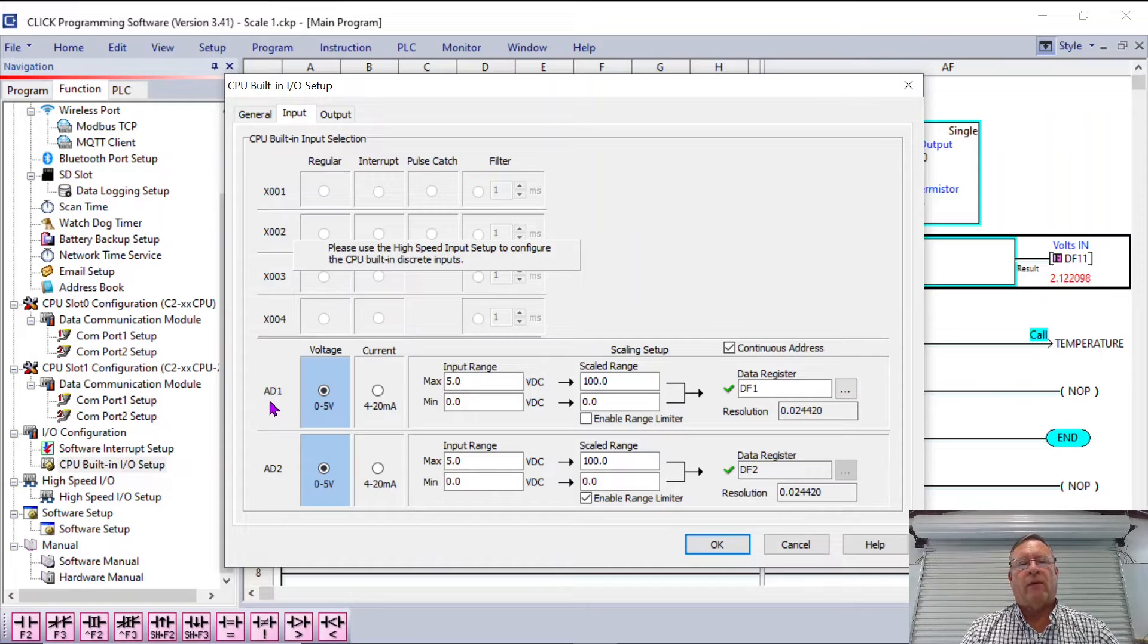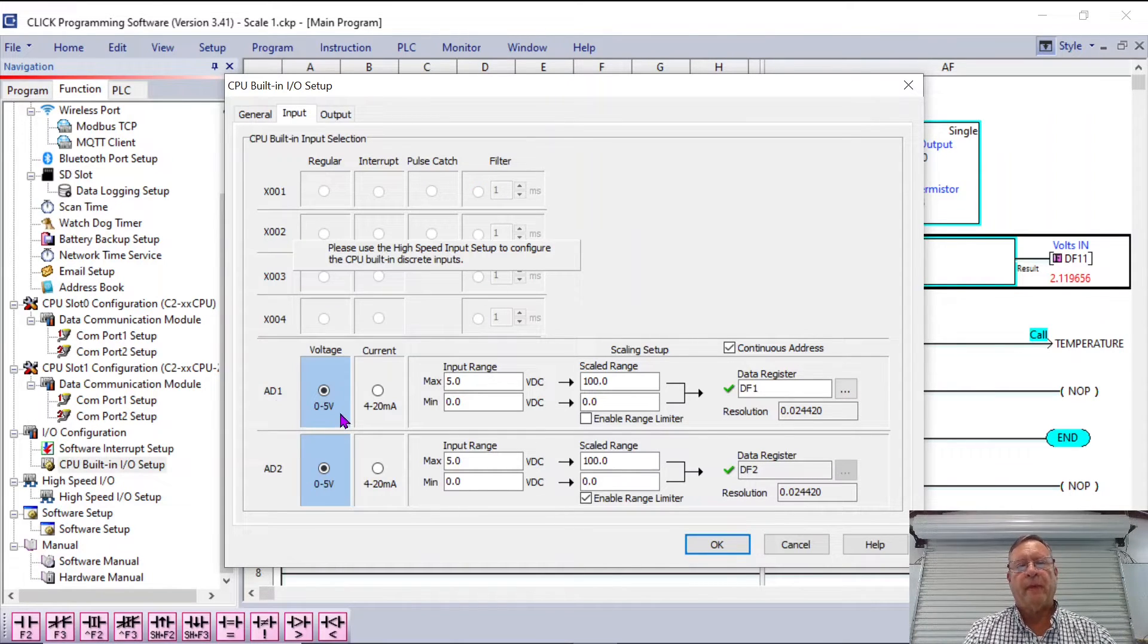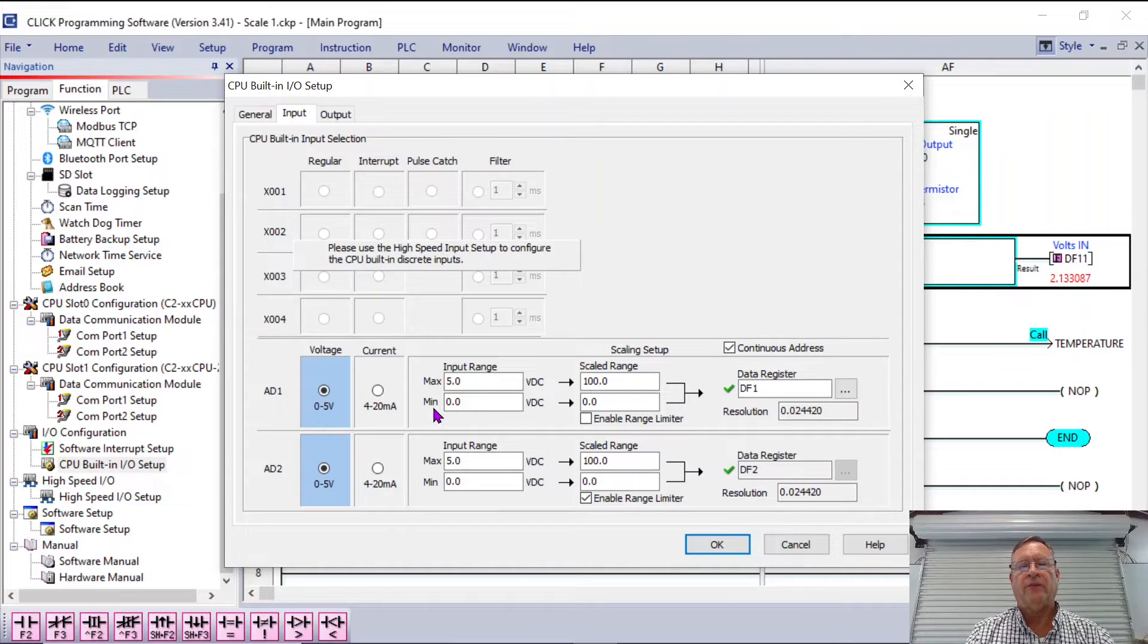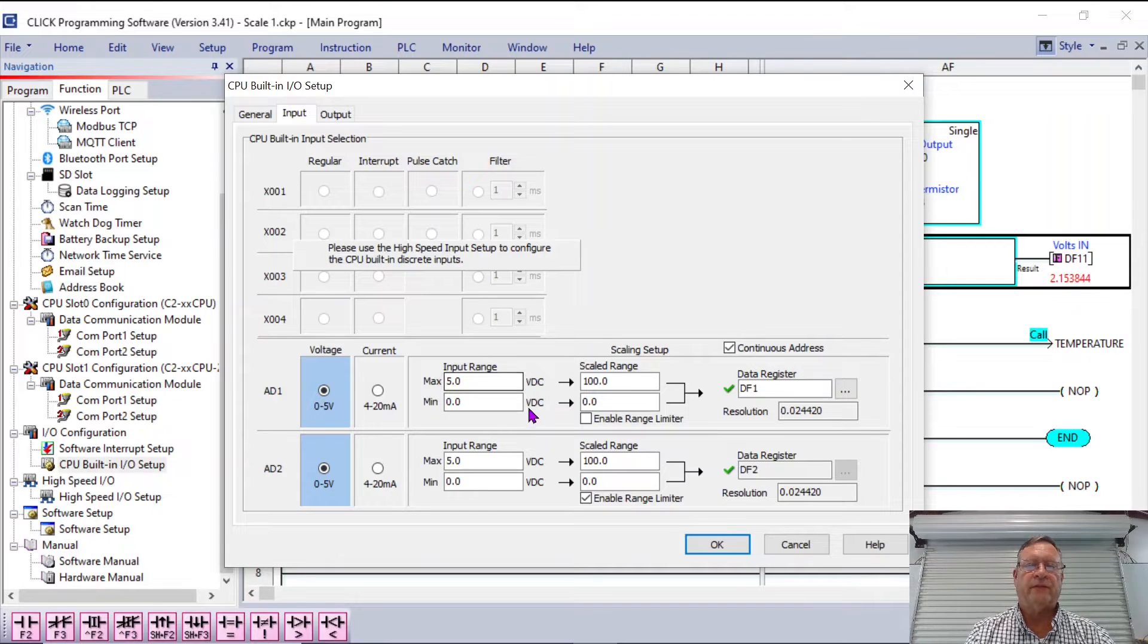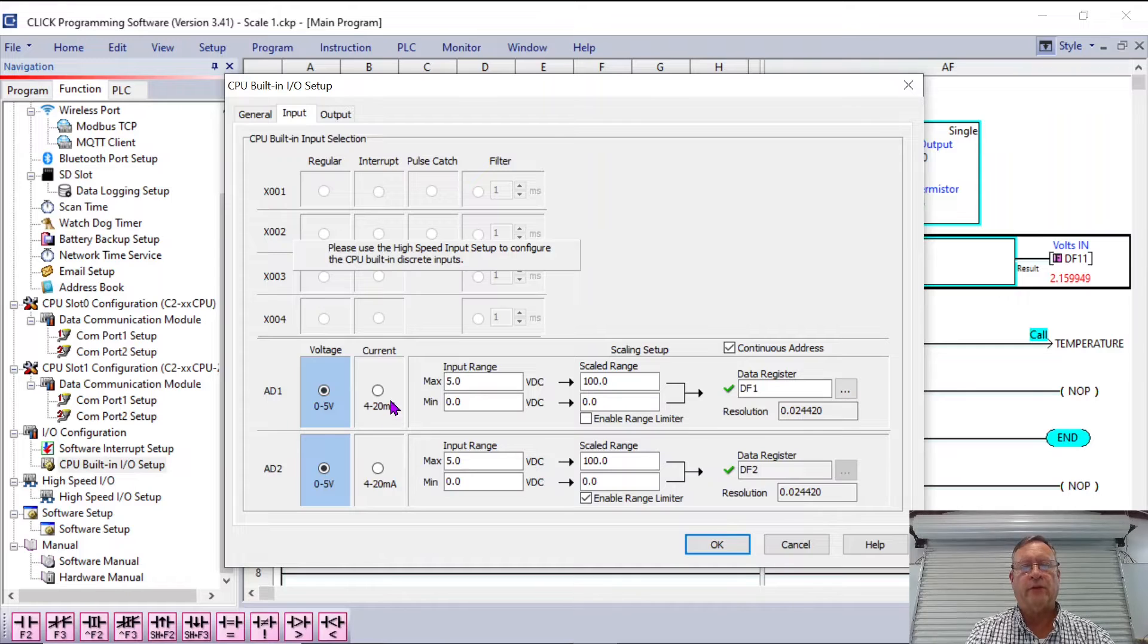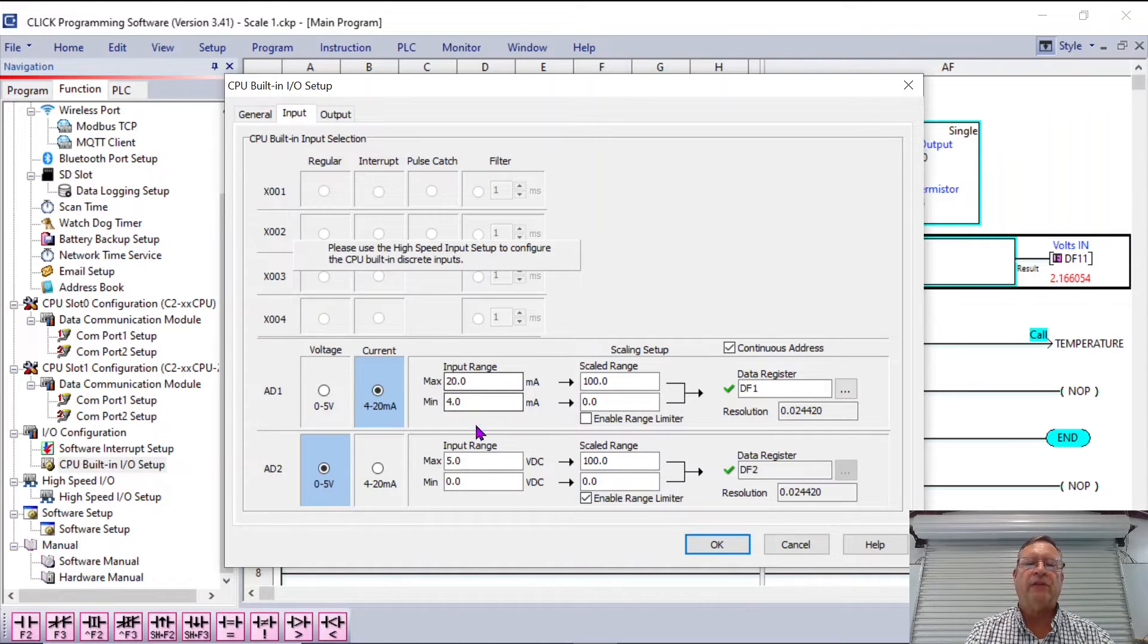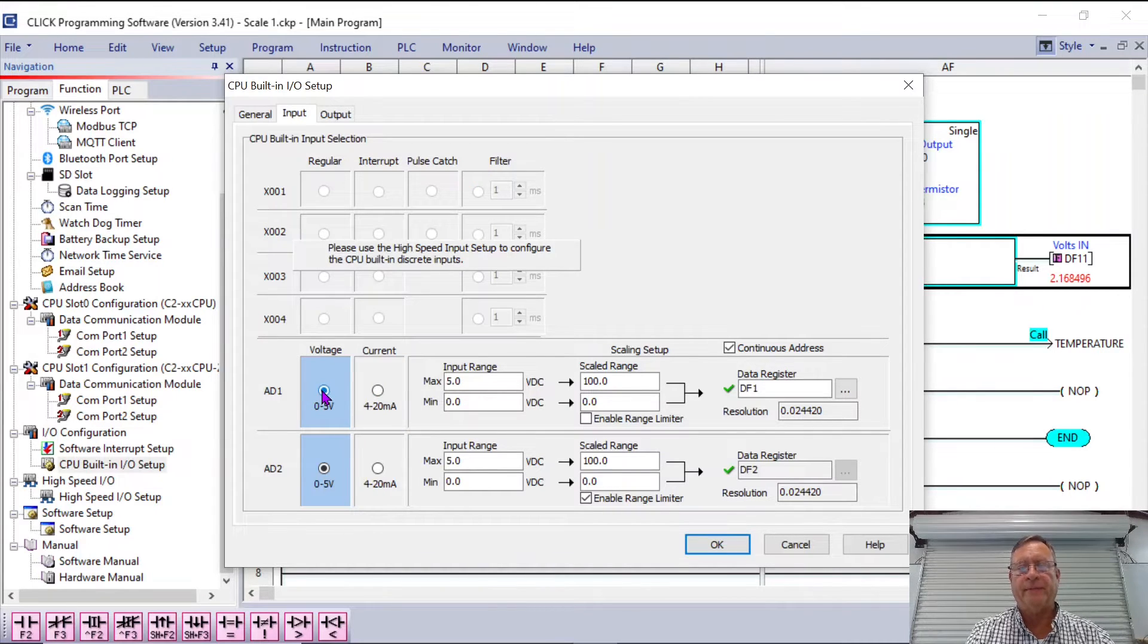On the analog to digital number one, I've selected the term, I'm physically connected to the terminal for voltage, that's zero to five volts. And that gives me a range of input range of zero to five. And that says this is in volts DC. What if I connected to this terminal, the second terminal for four to 20 milliamp input? There you see, this changes immediately on our input range, four to 20, and now it says milliamps. But I cannot change this value. This value is forced to be for whichever terminal that I've selected.